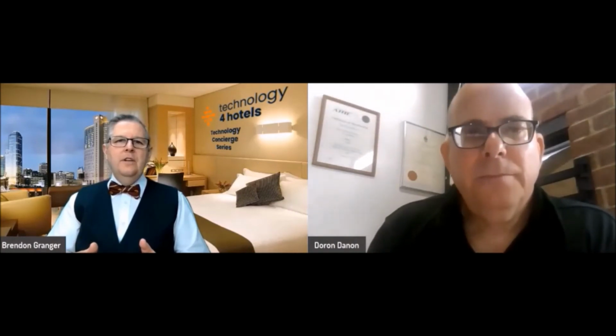So I think in summary, what you're saying is that with a good system, the door sensor detects if somebody has entered or exited the room. In conjunction with the motion sensor, it identifies there's someone in the room. And if it does, it says the room is occupied. When that room is occupied, the system doesn't have any control over the HVAC. The guest has full control, setting the temperature to whatever they want. And as you said, it doesn't matter how light a sleeper they are, because the room is occupied and the energy management system doesn't have any control, there's no way it would turn off.